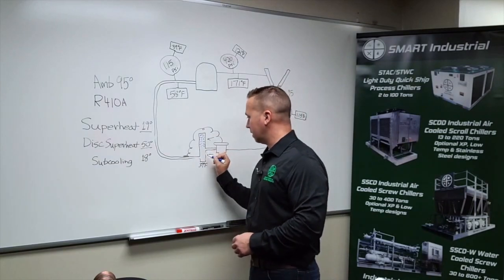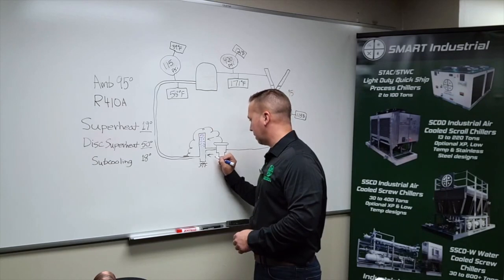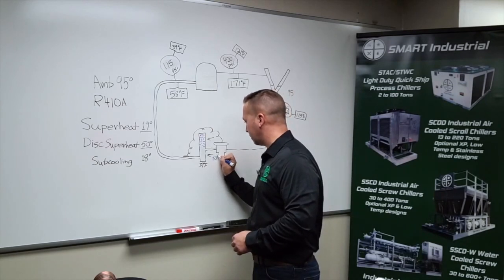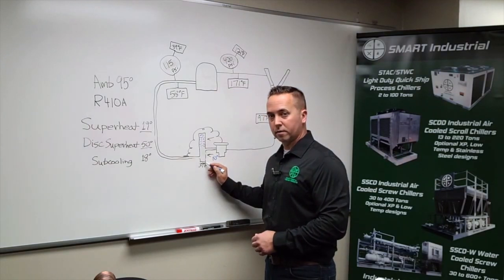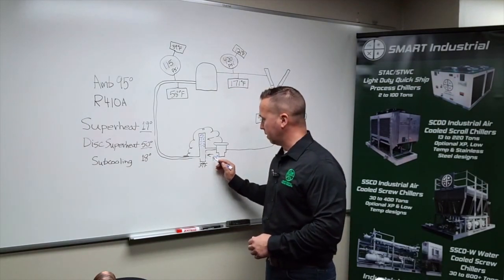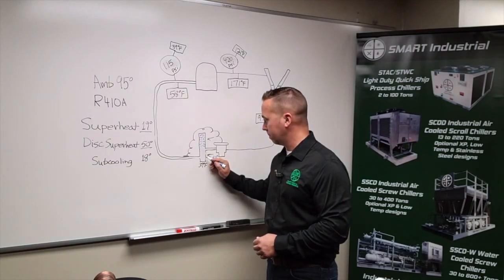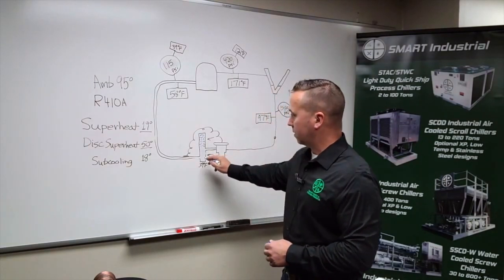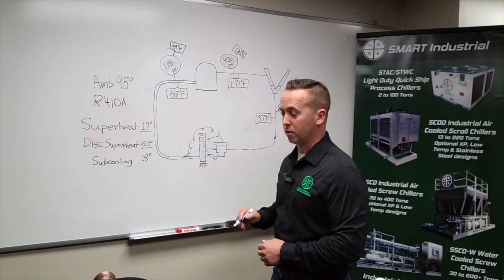And now I've continued to add heat because my air temperature may be at this point around 80 degrees Fahrenheit. With a coil temperature of 39 degrees, there is going to be plenty of heat coming from the air into the refrigerant. That heat is called superheat. Heat gained after the state change.